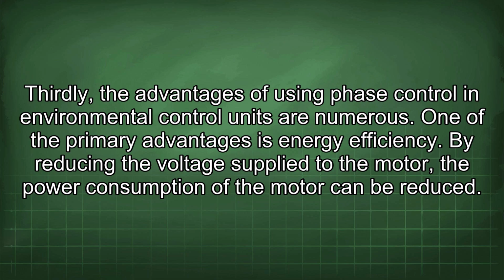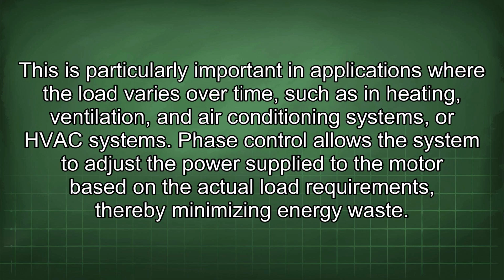Thirdly, the advantages of using phase control in environmental control units are numerous. One of the primary advantages is energy efficiency. By reducing the voltage supplied to the motor, the power consumption of the motor can be reduced. This is particularly important in applications where the load varies over time, such as in heating, ventilation, and air conditioning systems, or HVAC systems. Phase control allows the system to adjust the power supplied to the motor based on the actual load requirements, thereby minimizing energy waste.